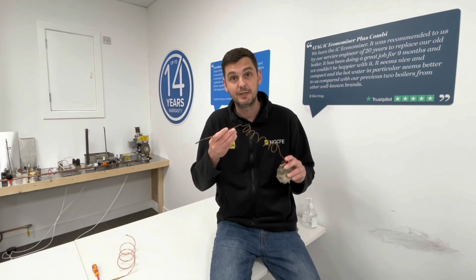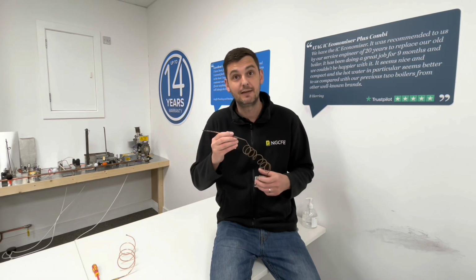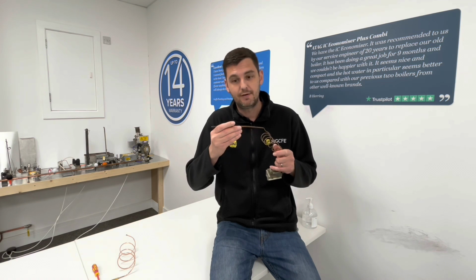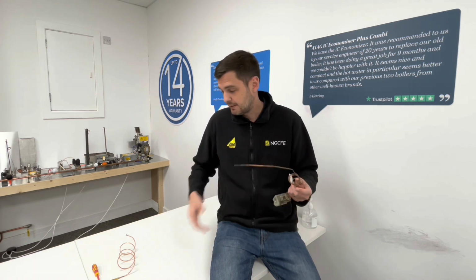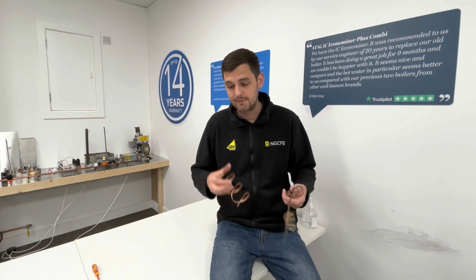And that's liquid expansion. It can be used as a thermostat, or it can also be used as a form of flame supervision device, in which case you've got a phial monitoring the presence of a flame, and it'll close the main supply of gas if the flame's extinguished. So now you've got an idea what we're going to be looking at, thermocouples, phials, and how they work. Let's look at the controls board.